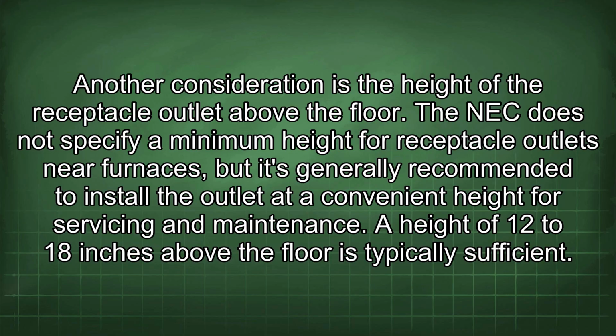Another consideration is the height of the receptacle outlet above the floor. The NEC does not specify a minimum height for receptacle outlets near furnaces, but it's generally recommended to install the outlet at a convenient height for servicing and maintenance. A height of 12 to 18 inches above the floor is typically sufficient.